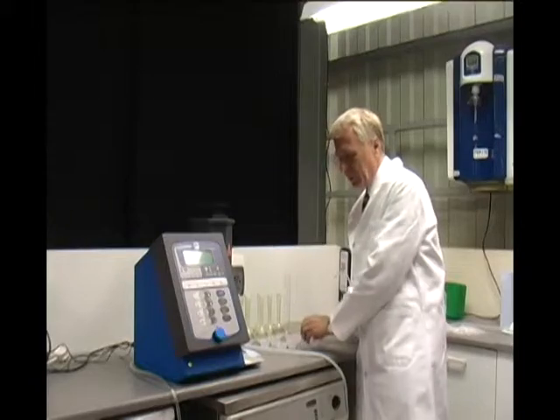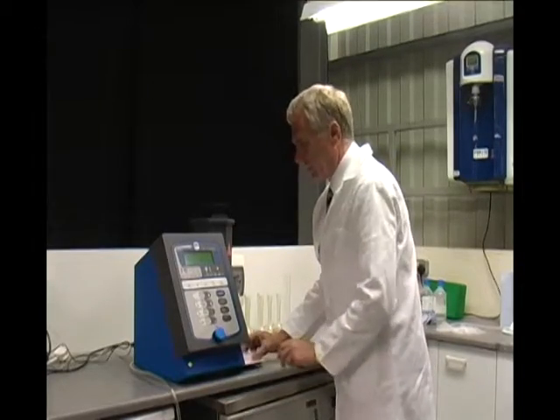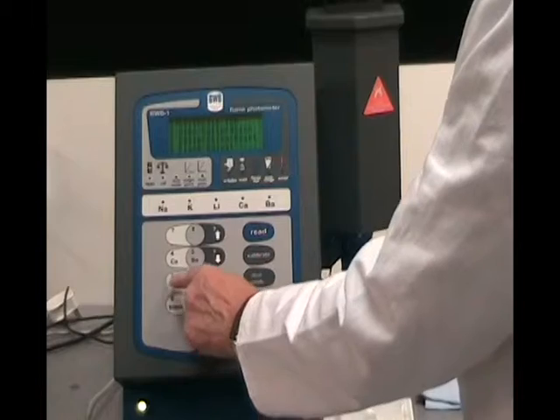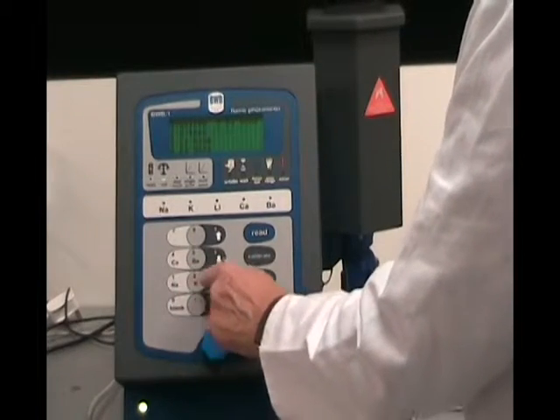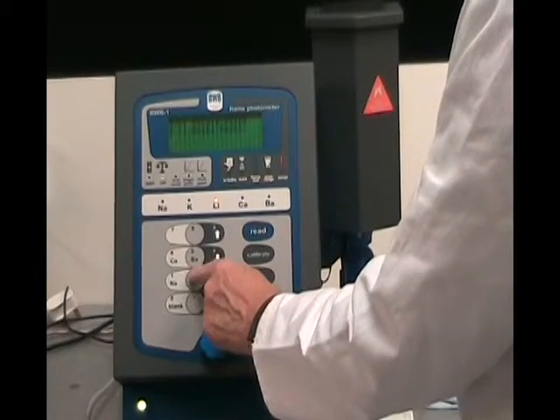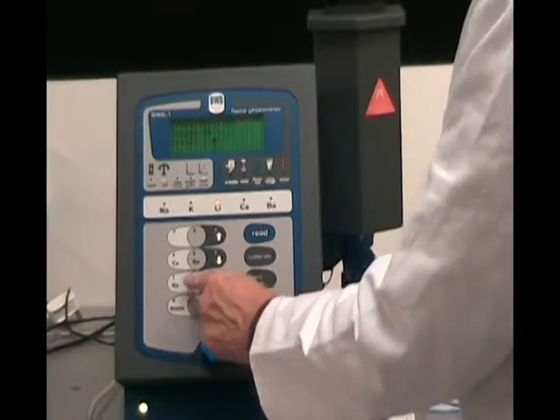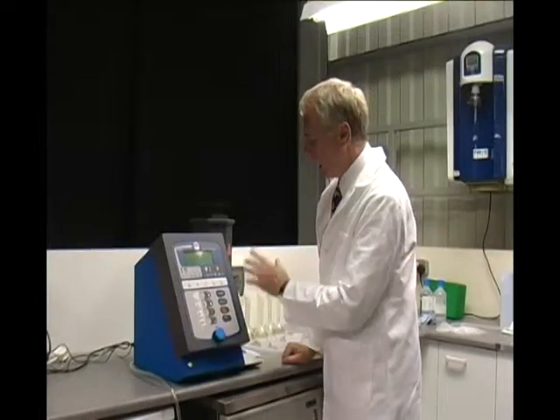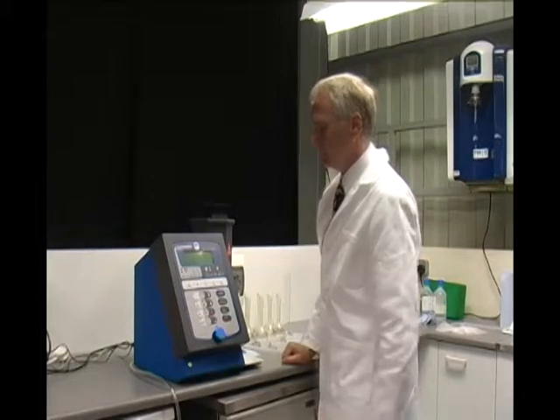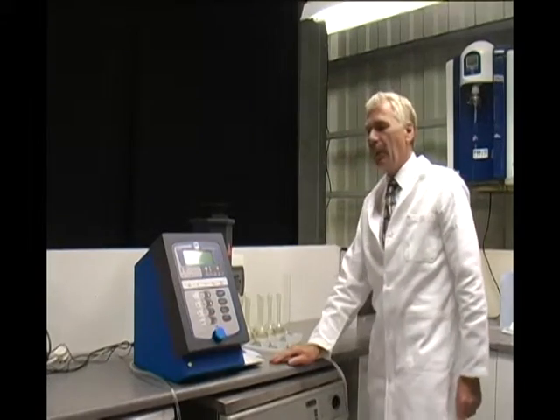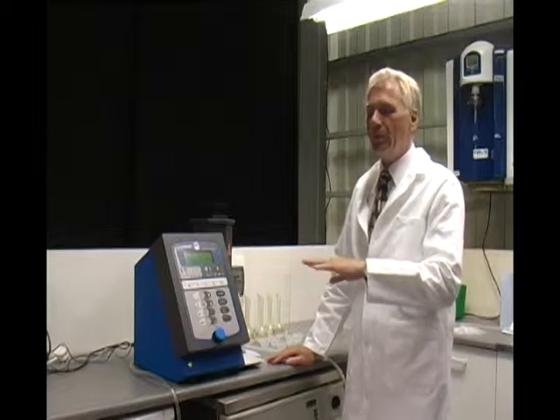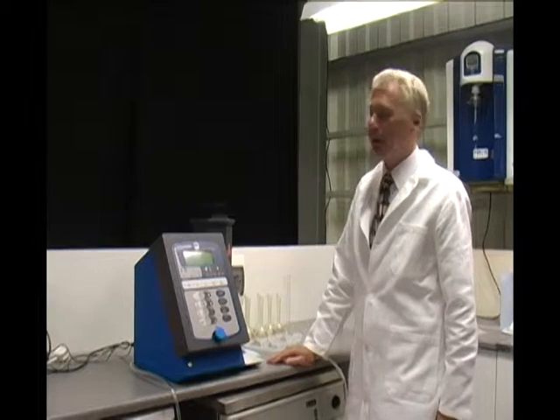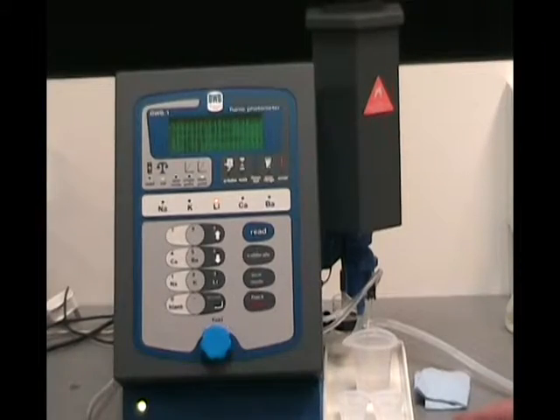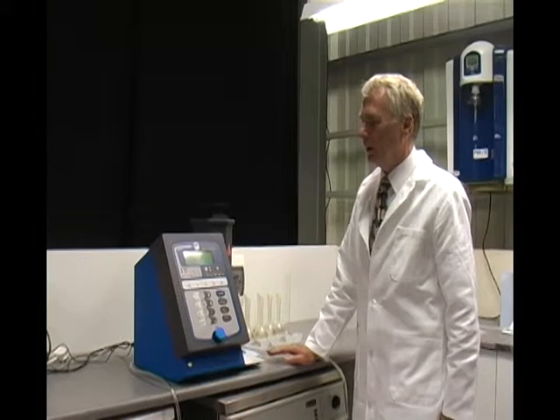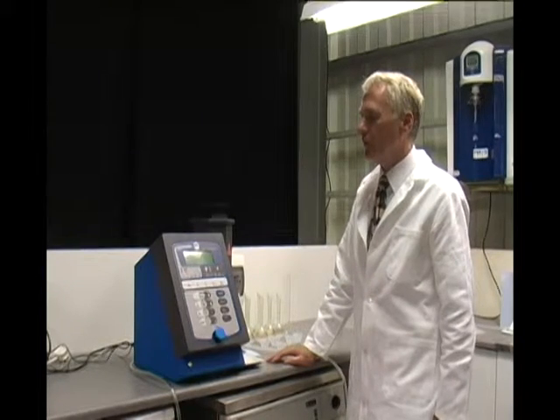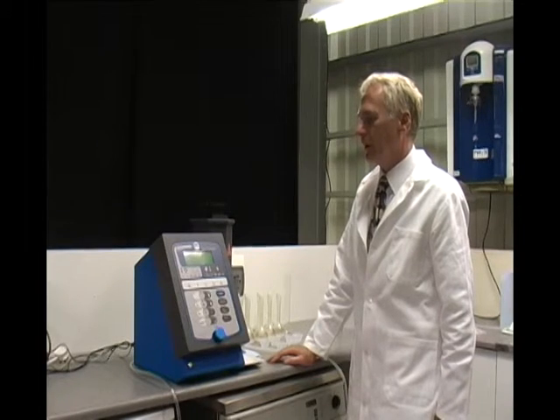Lastly, I'm going to calibrate lithium. So it is exactly the same process. Select 1 for calibrate ion, select 3 for lithium, 2 for multi-point, 2 for the number of points, and start aspiration of the blank. The system allows a period of time to flush the chamber and let the reading stabilise before it takes the reading that it requires for the calibration. The system itself will determine when it's ready to take the reading. There is nothing you need to do.